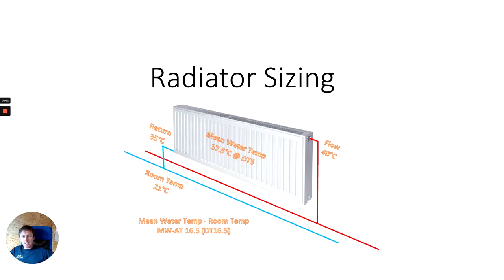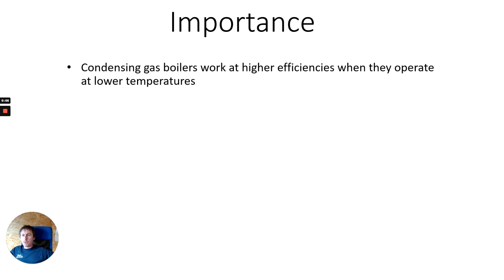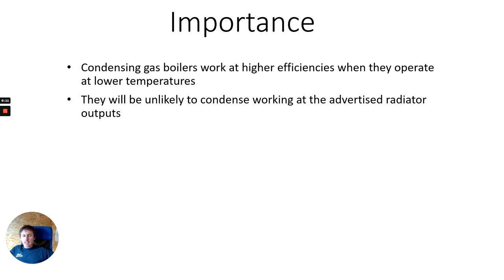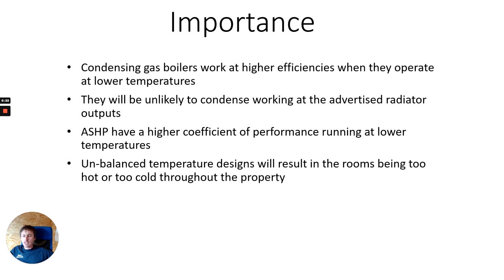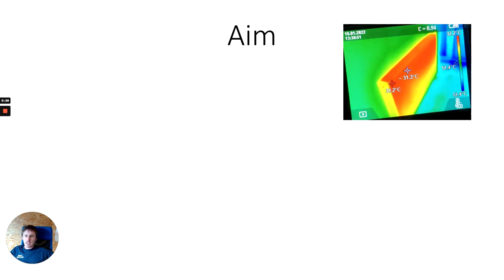Hi, thanks for tuning in for this presentation on radiator sizing. Condensing boilers work at higher efficiencies when they operate at lower temperatures, and they'll be unlikely to condense working at the advertised radiator outputs. Also, heat pumps have a higher coefficient of performance running at lower temperatures, and their COP is reduced if they're running too hot. Unbalanced temperature designs will result in rooms being too hot or too cold throughout the property.